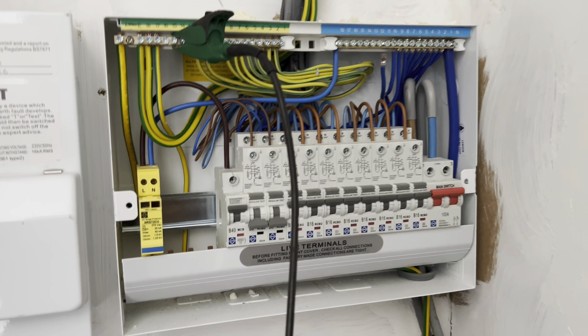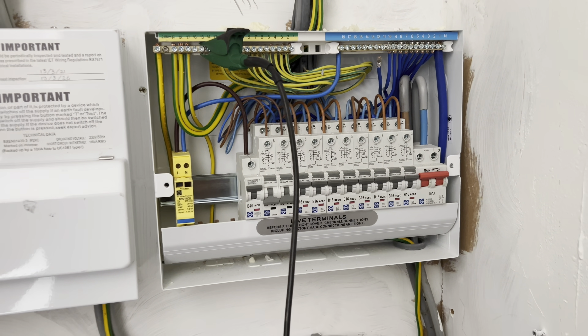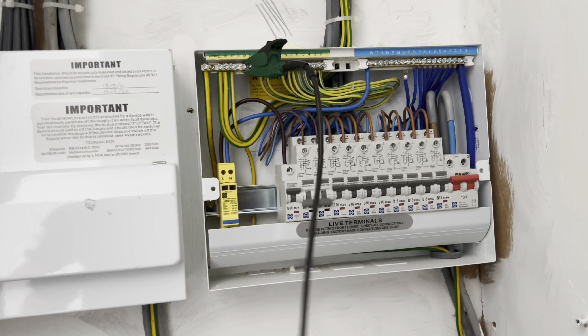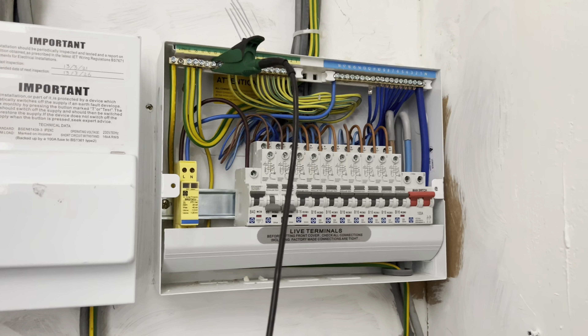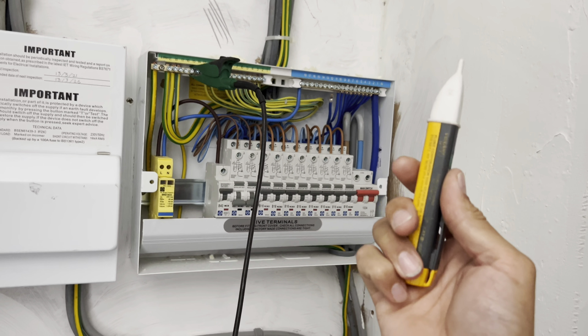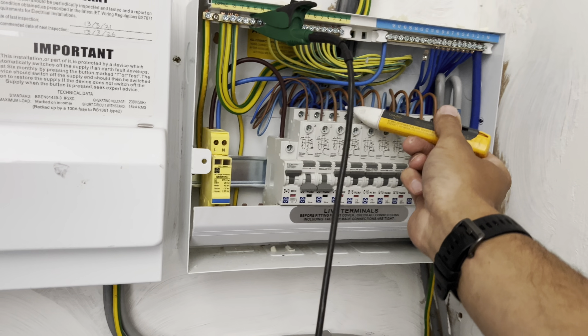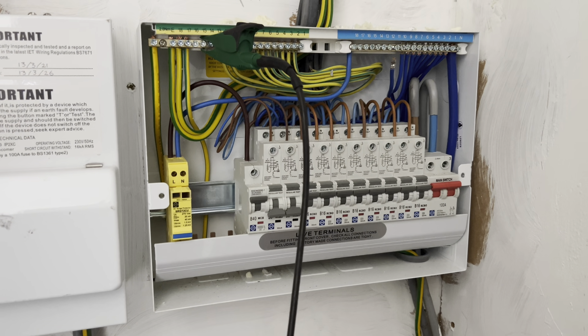If you're not technically minded, all you need to know is that I plugged in everywhere, took all the readings needed to make sure I had an earth path everywhere. And my tester also does a polarity check — when you take a Zs reading, which is your loop impedance reading on a socket, it will automatically do a polarity check at the same time and let you know if anything's adrift. So I wanted a second opinion, so I brought out my trusty volt stick. You don't use this to confirm definite voltages, but it's a nice easy way of looking at things. Ultimately the multifunction tester is king and gives you the results, but I always like a second form just to reiterate my thoughts.